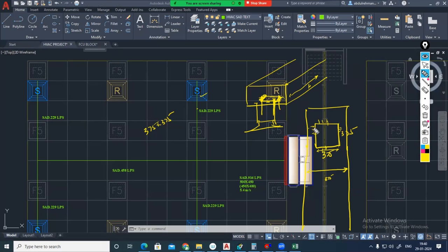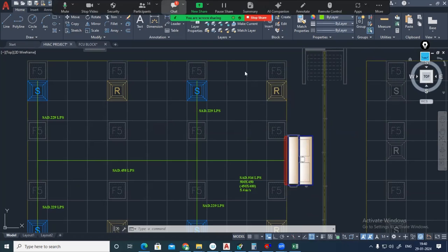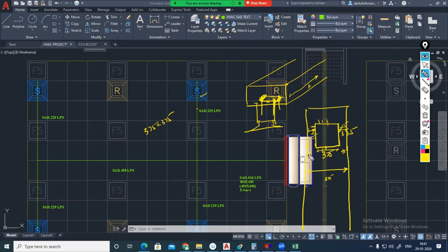But hammering in this side, 25 mm minimum allowance here, 25 mm minimum allowance here. So that's why if your diffuser neck size is 375, you need 25 plus 25, 50 mm. Yes, the collar, exactly. So 375 plus 25, 375 plus 25. As you know, multiples of 25 duct we are normally not purchasing. Multiples of 50 we have to purchase. That's why if you want to make a rigid duct drop, a collar from the duct bottom, the minimum width of this duct should be how much? 50 mm more. Then only you can take the drop there. 450 mm. Keep that in mind accordingly.